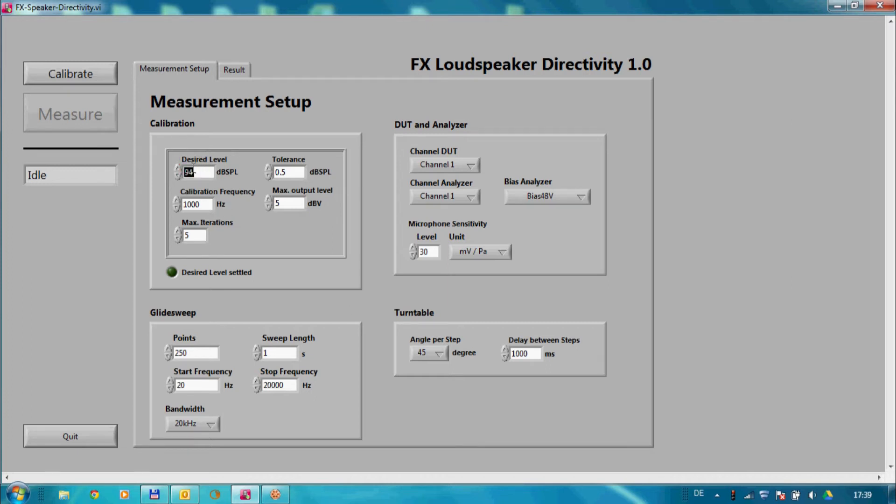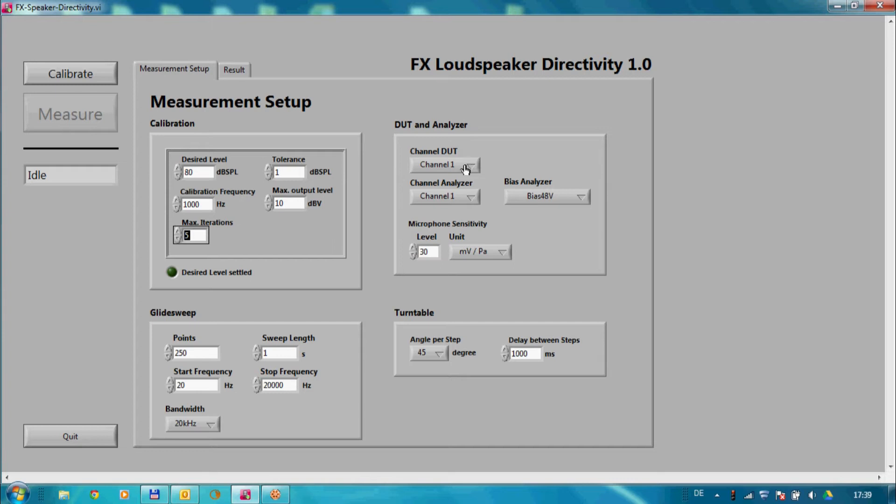First, I specify the desired sound pressure level to calibrate our setup. Then, I set the calibration frequency, the maximum tolerance range, and the maximum output level to prevent damage of the DUT as the generator level goes up.